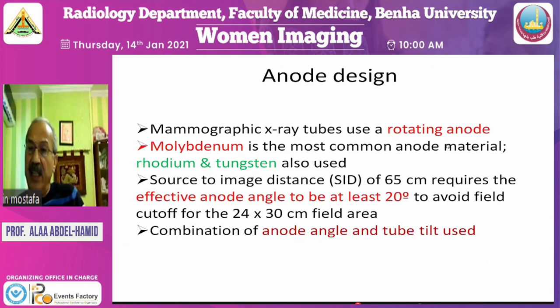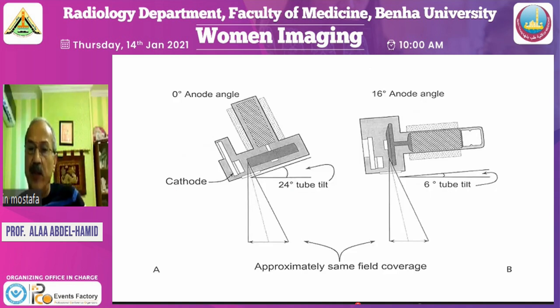The anode design is a rotating anode for cooling, and it is formed of molybdenum. Some machines use rhodium or tungsten, but molybdenum is the most commonly used type. The source to image distance is 65 centimeters, and this needs effective anode angle to be 20. The effective anode angle here, if we use the straight anode angle here, we have to have a big tube tilt about 24 degrees in order to get a proper image size up to 24 by 30 centimeters. But with the beveled angle, we have here to diminish the tube angle, and the anode angle here is, although it is low, it can cover the same distance as that of the straight anode angle.